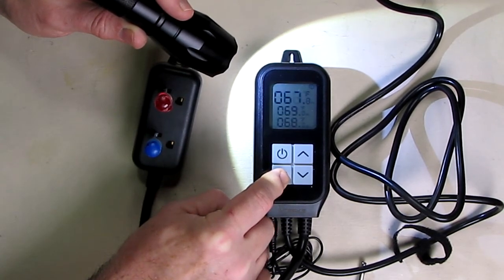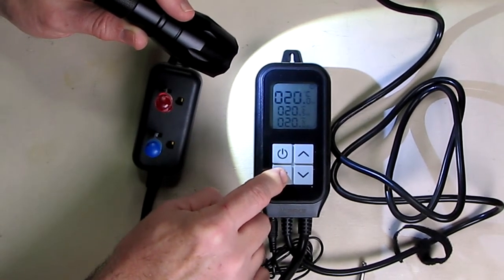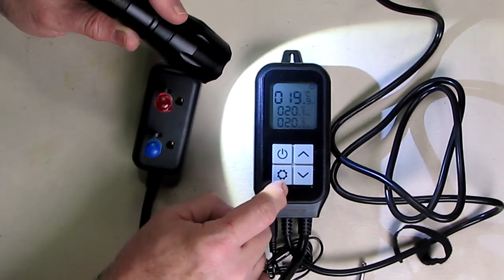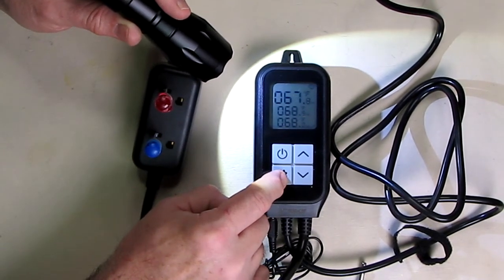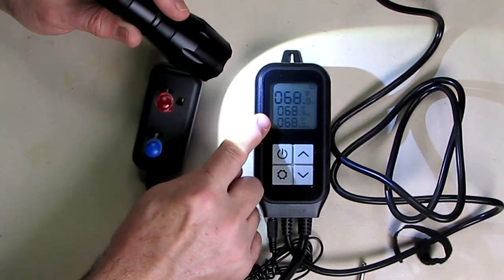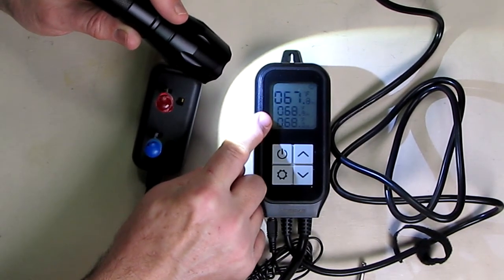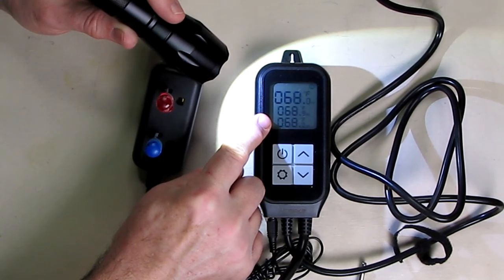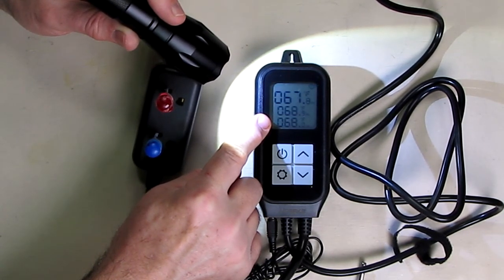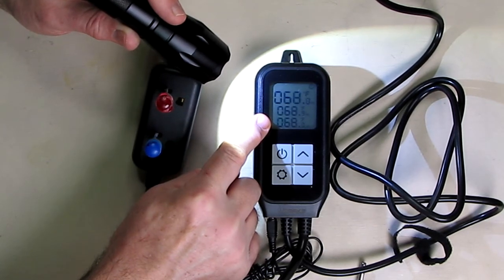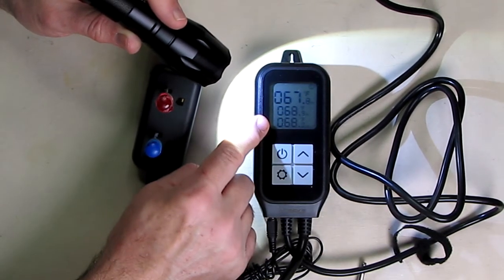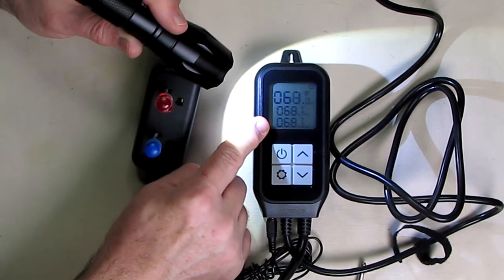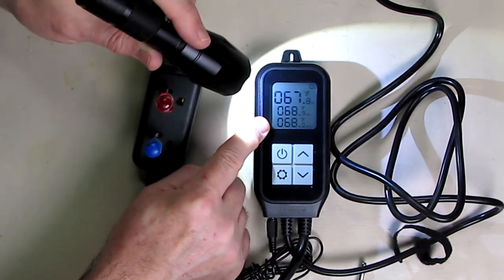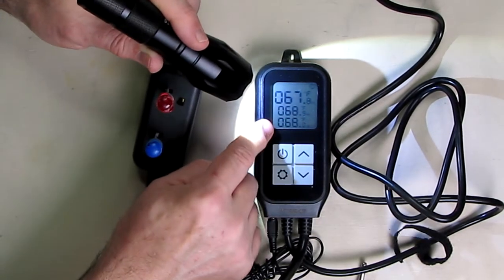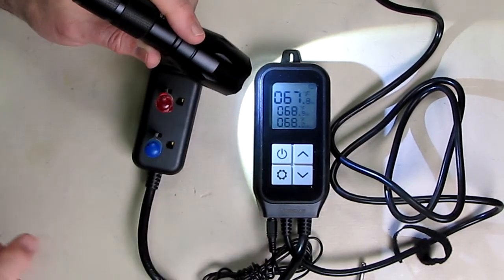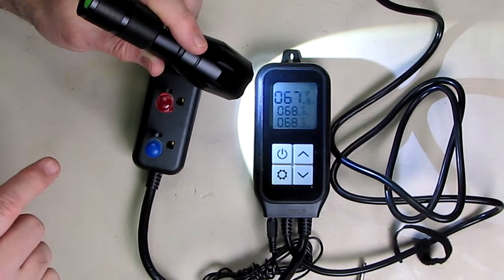Once we reset this, we can pulse this to go to Centigrade versus Fahrenheit. The idea is it's not going to let you have a really wide range here, because the whole point is to control something within a couple degrees Fahrenheit or Centigrade. So you want your temperature range to be really close, like in this case 68 degrees on both the cool and the hot side, and we're going to demonstrate that.